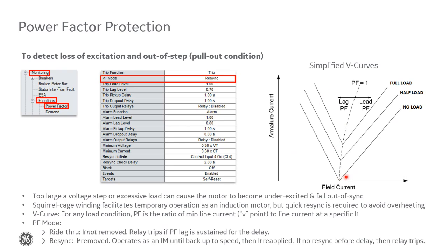If you increase the field excitation, the stator current will still increase, but this time with a leading power factor. So this side is the leading power factor section. And this part here is the concept for synchronous motors being used unloaded as synchronous condensers for power factor correction. So for any load, the power factor is the ratio of this minimum stator current point to what the stator current actually is per what the field excitation is.